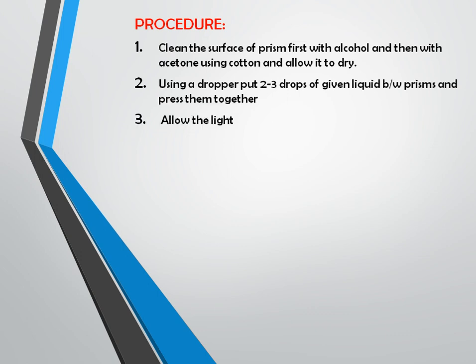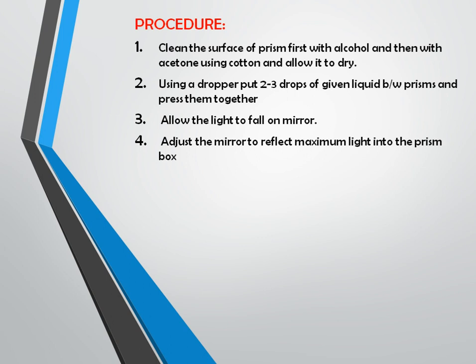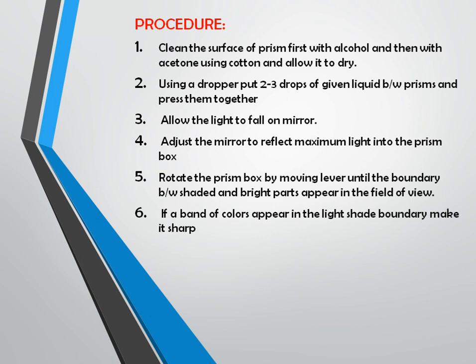Procedure for measuring refractive index: first, clean the surface of the prism with alcohol and then acetone using cotton, and allow it to dry. Then, using a dropper, place two to three drops of your sample between the two prisms. Allow light to fall on the mirror and adjust the mirror to reflect maximum light onto the prism box. Then rotate the prism box by moving the lever until the boundary between the shaded and bright parts appears in the field of view. If a band of color appears at the light-dark boundary, make it sharp by rotating the compensator.